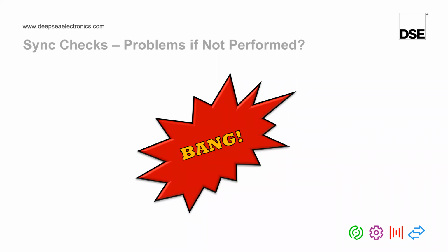So whenever you have any form of load sharing issue or synchronizing issue, the first thing that we would advise you do at DeepSea is do these 4 steps to synchronizing. I would say 95% of the time, if you do the DSE 4 steps to synchronizing, you will find your problem. And by finding the problem and doing the 4 steps, in most cases, you will also fix the problem. The other advantage of the DSE 4 steps to synchronizing is you're not necessarily just testing the DeepSea module and its calibration. You're also testing the generator as a whole.